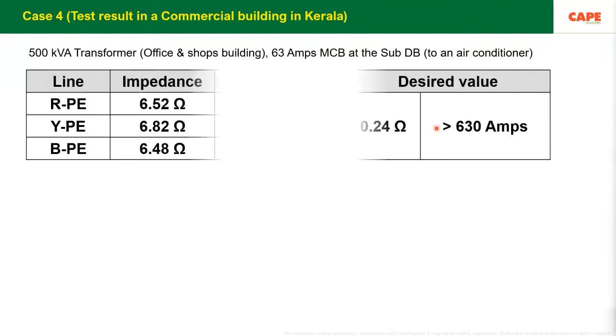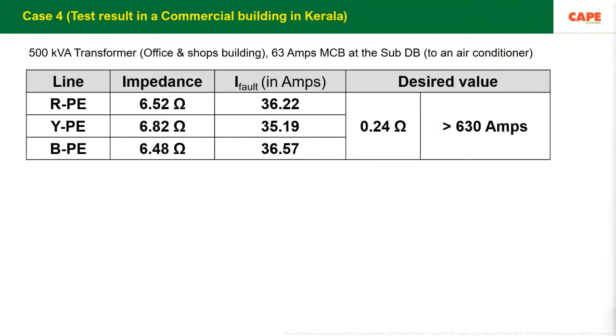I put the meter into his distribution board and tested it. It was a 63 amps MCB in a sub distribution board. The building owner had given an MCB DB to this particular shop, which had a 63 amps MCB. Plus, additionally, there was a 10 amps single pole MCB for some of his light fittings. Now, this gentleman had connected an air conditioner to this 63 amps MCB. He took 4 square mm wire and connected it to the air conditioner. So I tested the terminals of the outgoing of this particular MCB.